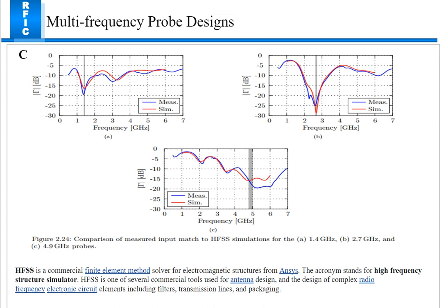Multiple frequencies rather than a single frequency must be used to differentiate temperature received from various depths in the tissues. The additional challenge is that the probe must be receiving power from the same part of tissue, or at least in a manner that ensures the model is still valid. The model assumption is that the tissue is a stack of homogeneous tissue layers that are infinite in extent in the transverse direction, with uniform temperature in the transverse direction.